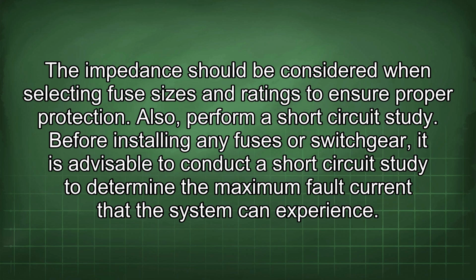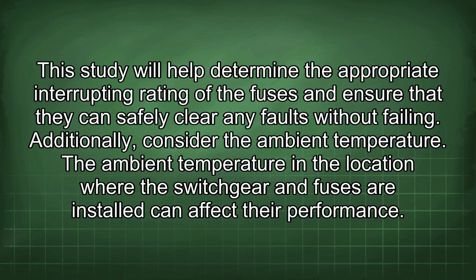Before installing any fuses or switchgear, it is advisable to conduct a short circuit study to determine the maximum fault current that the system can experience. This study will help determine the appropriate interrupting rating of the fuses and ensure that they can safely clear any faults without failing. Additionally, consider the ambient temperature.